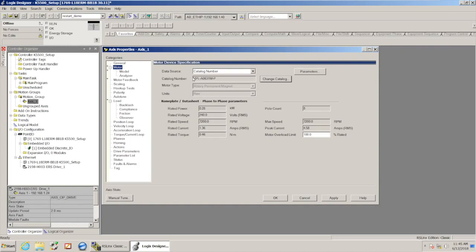So when I enter in that catalog number, that gives Logix all the information about that motor. So all of the information about the voltage, the power, the current, everything that that motor can handle, it's all populated in there now by adding in that catalog number.